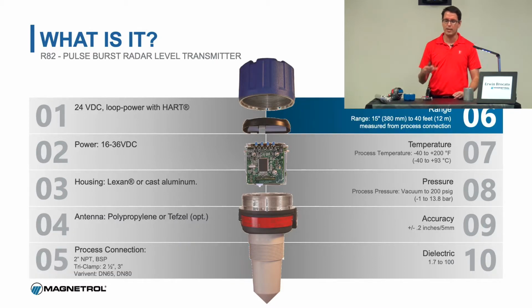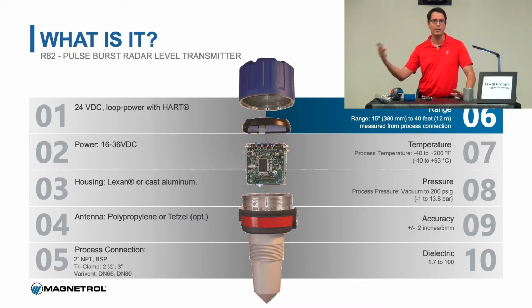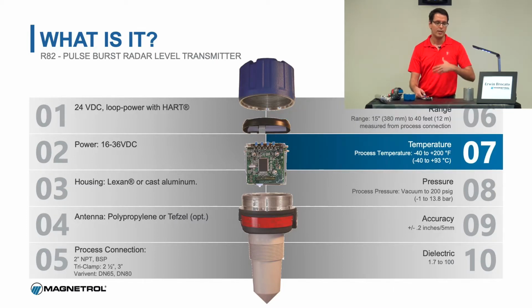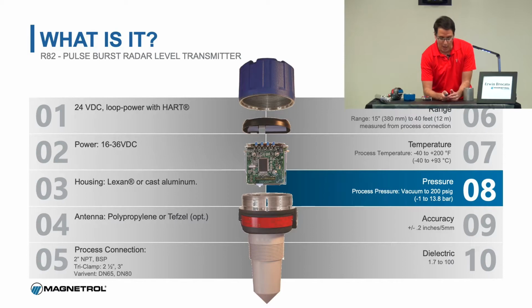There is a limit on the range of the device. Obviously, it is the lower cost model, so we can only probably go about, I want to say, 40 feet with this device, which sounds like a lot, but the higher end models can go up to 100 feet. So there are some limitations to this particular product. There are limitations on temperature: 200 Fahrenheit is the max. Limitations on pressure: we can go up to 200 PSI on the device. On the higher end models, you can go up to much higher pressures, obviously.